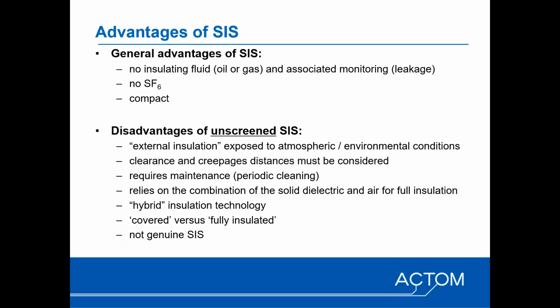Firstly, there's no insulating fluid or gas, and therefore no associated monitoring or leakage to worry about. No SF6, so it certainly is a good alternative to SF6. And because of the dielectric properties of solid insulating materials with a high breakdown strength, high kV per millimeter, you can design switchgear that is relatively compact.